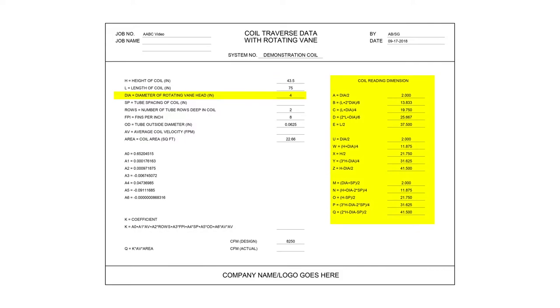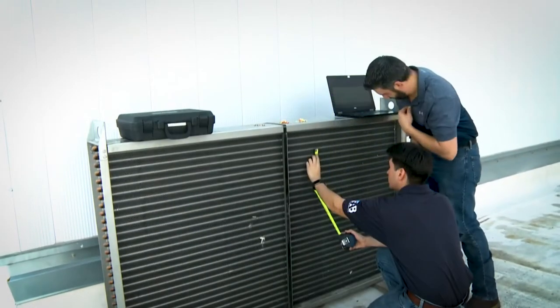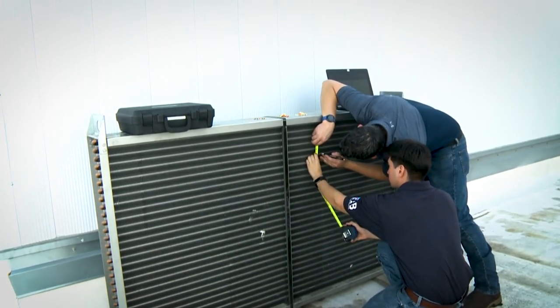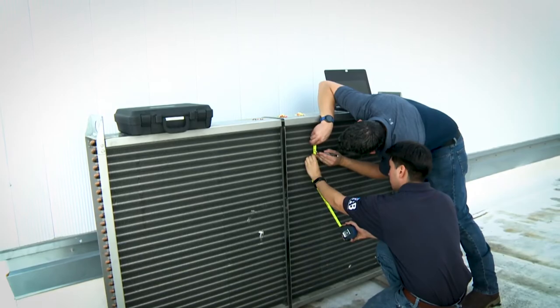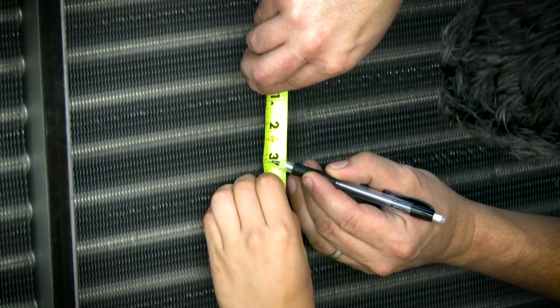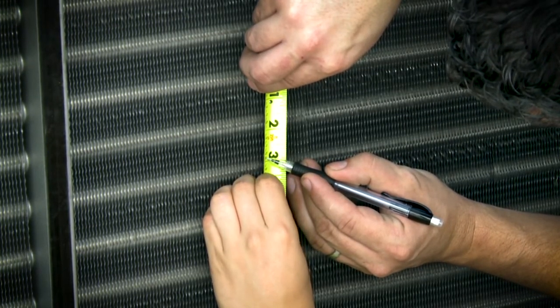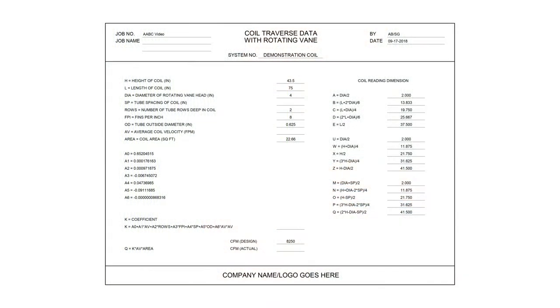Notice the coil reading dimensions on the right are automatically calculating. The AHU-1 submittal data did not include the tube spacing of the coil. The tube spacing of the coil was measured as 0.875 inches. Record the measurement in the form: SP equals tube spacing of coil as 0.875 inches.